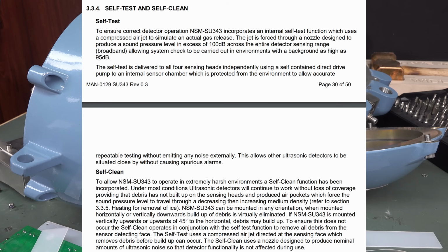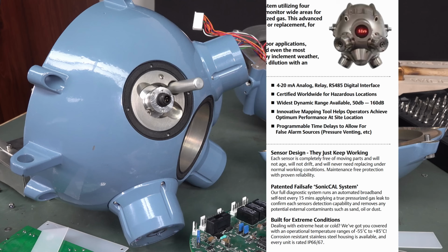It has a patented failsafe SonicCAL system. Our fully diagnostic system runs an automated broadband self-test every 15 minutes, applying a true pressurized gas leak to confirm each sensor's detection capability and remove any potential external contaminants such as sand, oil, or dust.